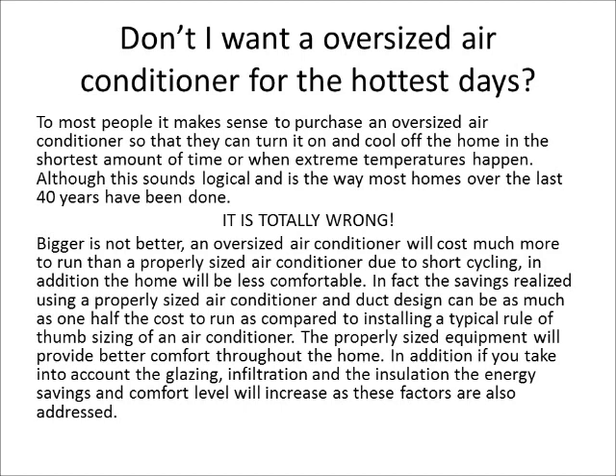Don't you want an oversized air conditioner for the hottest days? To most people it makes sense to purchase an oversized air conditioner so they can cool off the home in the shortest amount of time or during extreme temperatures. Although this sounds logical and is the way most homes over the last 40 years have been done, it's totally wrong. Bigger is not better. An oversized air conditioner will cost much more to run than a properly sized one due to short cycling. The home will also be less comfortable. In fact, the savings using a properly sized air conditioner and duct design can be as much as half the cost to run compared to a typical rule-of-thumb sized unit. Properly sized equipment provides better comfort throughout the home and accounts for glazing, infiltration, insulation, energy savings, and comfort.